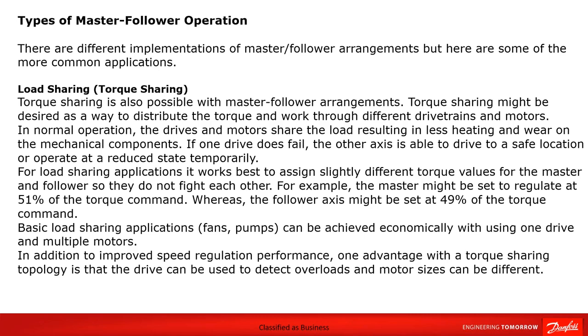Now for load sharing applications, it's better to assign what we call slightly different torque values for the master and follower. In other words, if you put them the same, they have a potential to fight each other. So we don't want that to happen. We, for example, might set the master to regulate at 51% of the torque command, whereas the follower axes we might set at 49% of the torque command.